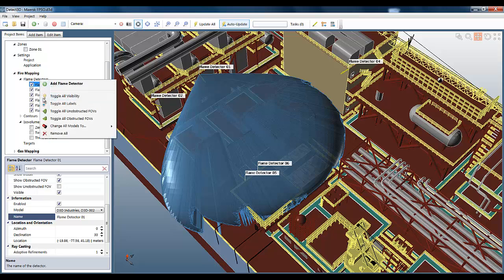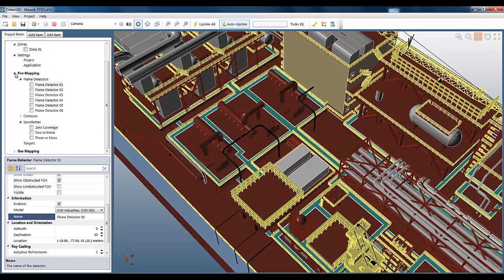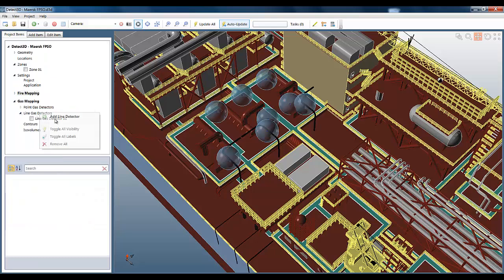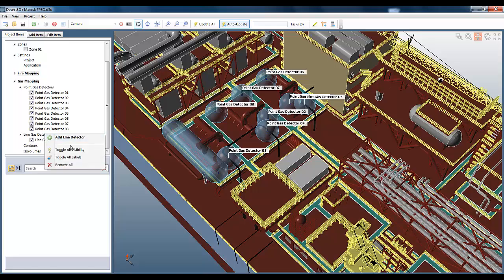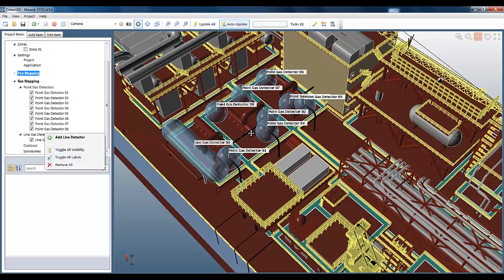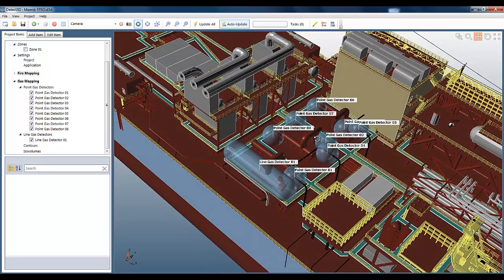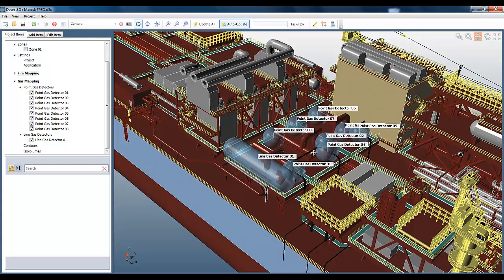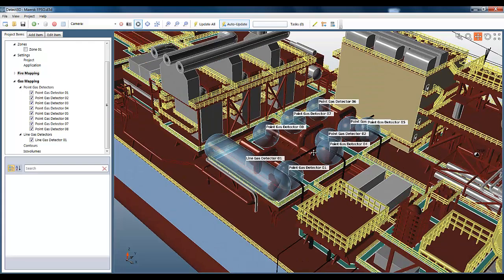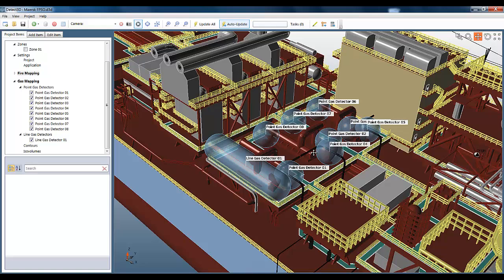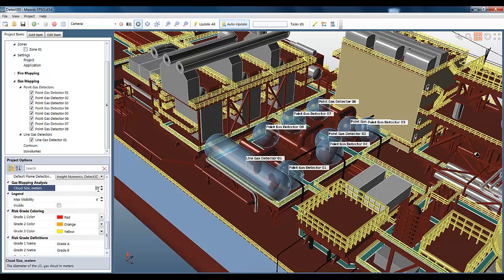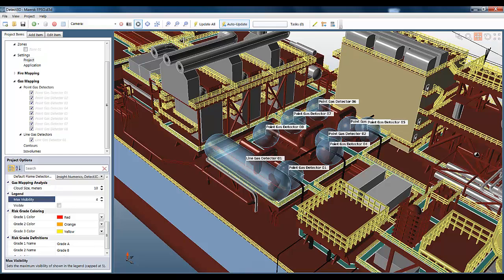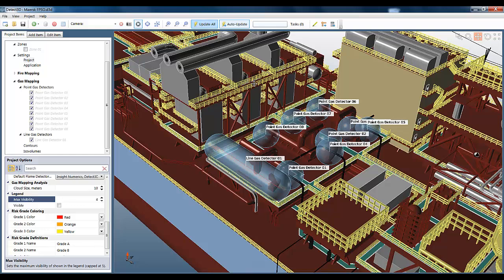Let's not forget about gas detectors. We've seen in the previous videos that you can add point and open path or line gas detectors in Detect3D, and I've added some here. However, gas detectors don't have a field of view, so the options are somewhat more limited. The gas mapping is performed using a spherical gas cloud of a certain diameter. One thing you can do is to change the diameter of that gas cloud you're looking at. But as far as the make and manufacture of the gas detectors, well, these make no difference in Detect3D. It's just simply the size of the gas cloud. To demonstrate that, I've just changed the gas cloud size to 10 meters, and you'll be able to see all the blue fields of influence update there.